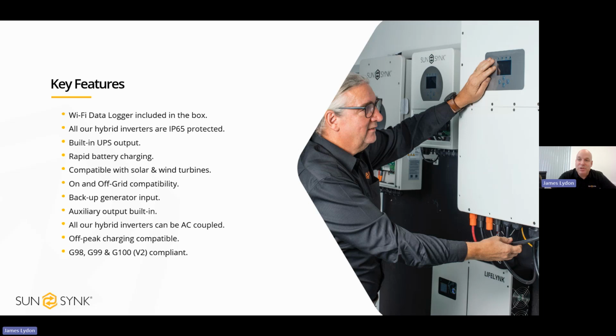If someone was completely off grid before, that backup generator might have been on 18 hours a day, let's say, for however long they needed power. But with our system, because it is charging the batteries and powering the load at the same time while it's on, it might only need to be on for a couple of hours.